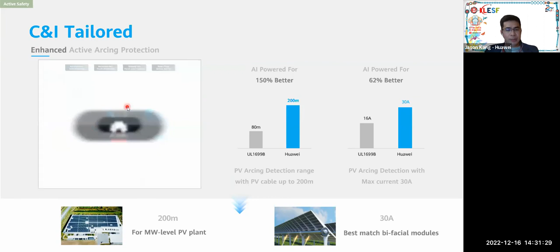So our inverter is equipped with AFCI, or the arc fault circuit interrupter. So these are the problems as I mentioned just now, which are pretty common. So our inverter, yeah, is packed with power electronics, and we also have AI capability, artificial intelligence, to accurately protect the PV system. So in the illustration over here, if let's say there's a PV arc that happens in this PV module, whereby this module is connected to the inverter over here. Okay, so with the data analysis using the AI, the inverter will be able to tell whether it's an actual arc fault or it's an interference that is happening within the perimeter of the PV system.